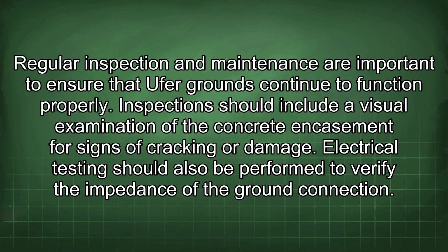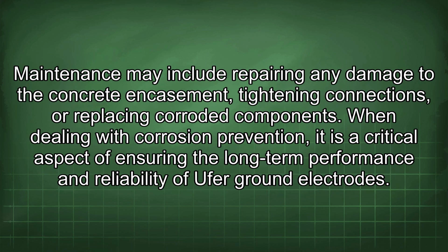Inspection should include a visual examination of the concrete encasement for signs of cracking or damage. Electrical testing should also be performed to verify the impedance of the ground connection. Maintenance may include repairing any damage to the concrete encasement, tightening connections, or replacing corroded components.